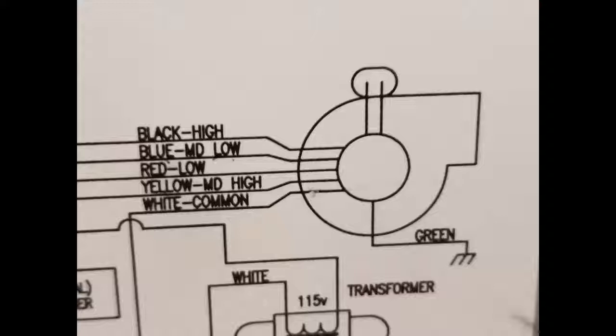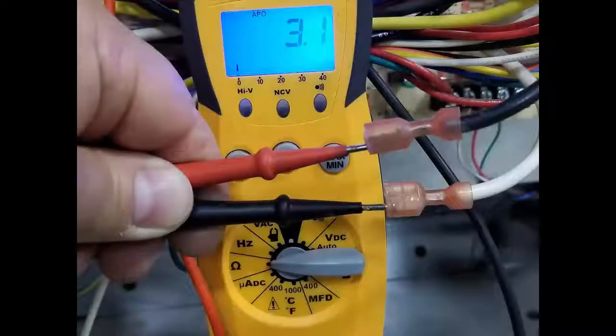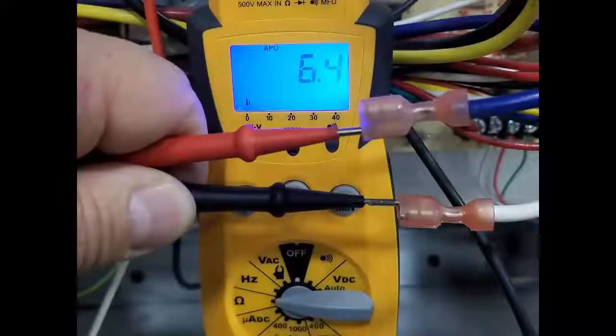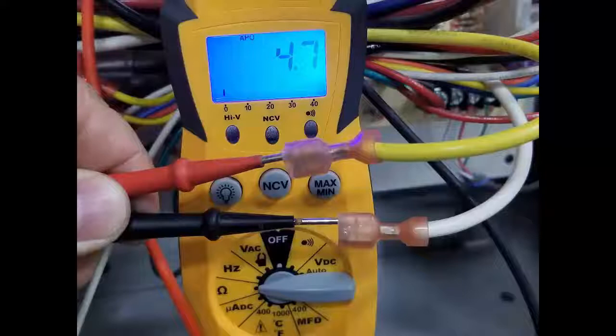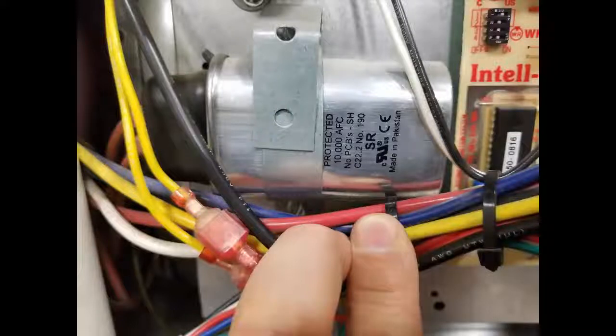All we have to do is find the speed leads. You can see in this particular case on the schematic, we have a black lead, a blue lead, a red lead, and a yellow lead, and then white is common. All I do is pull those speed leads off and check each one to common. In this case I'll start with black, then move to blue, then red, and then yellow. You should get some kind of ohm reading between each one of those speed leads and common. If you get an open line, then that motor has bad windings and should be replaced. If all of the speed leads check out and the motor's still not starting, then you probably have a bad start capacitor. And that's really easy to check also.